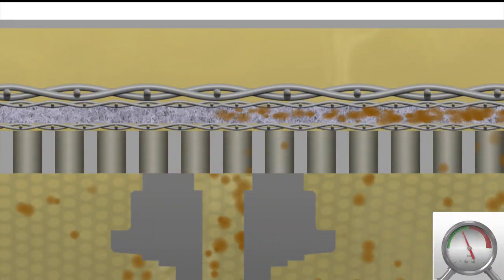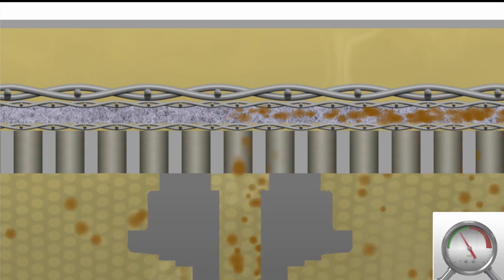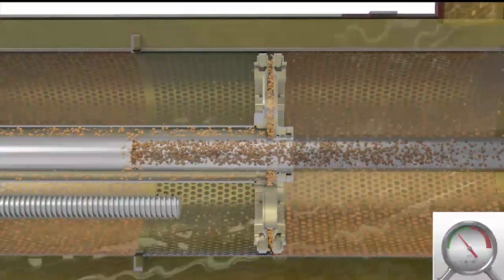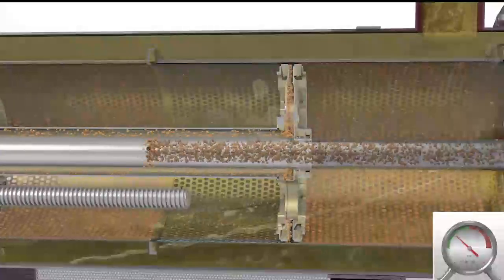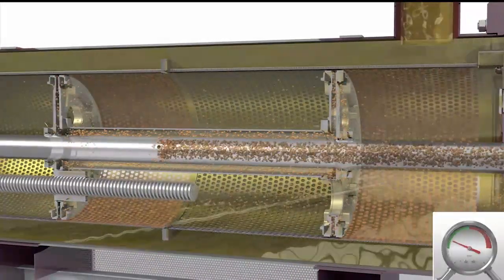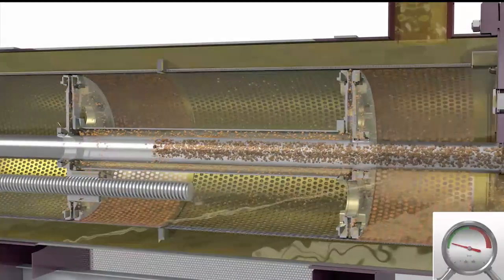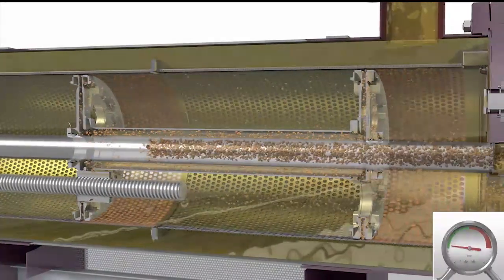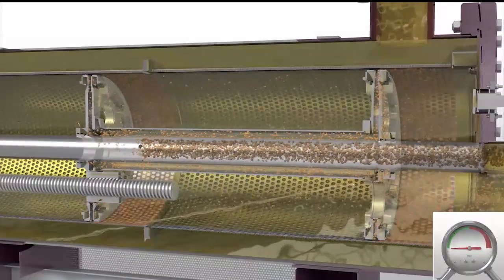The sealing rings of the backwash piston are pressed against the perforated drum, whereby the best possible sealing between unfiltrate and reject chamber is realized. Bypass flows are prevented, so the entire backwash flow has to go through the filter material. This guarantees lowest possible medium losses while providing the highest possible cleaning effort.